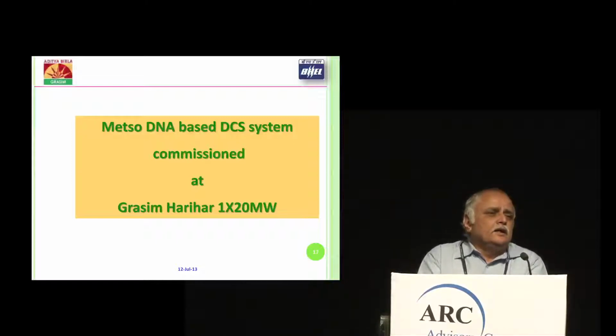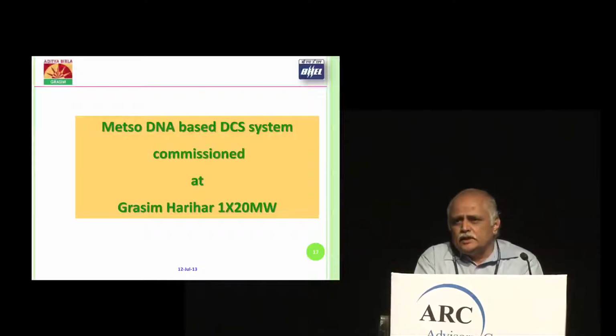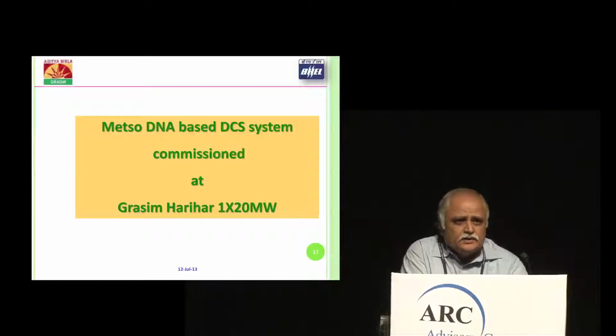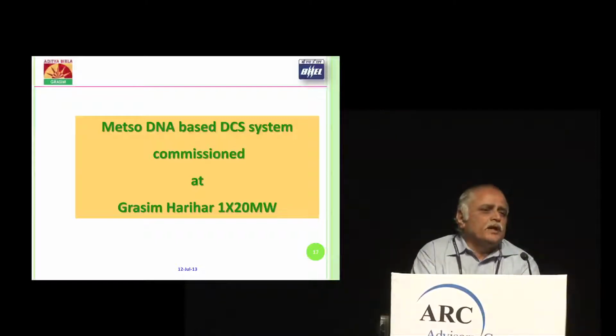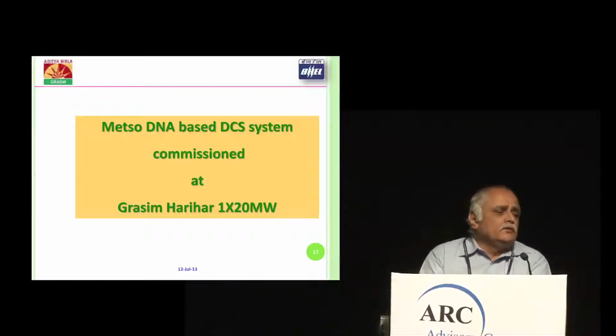When a sudden grid disturbance happens, the plant has to isolate itself and continue to support local internal requirements without disturbing the process. This is what we discussed yesterday as the islanding scheme. So islanding operation of the plant is also an essential requirement.